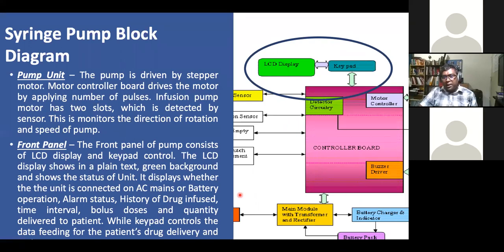On the block diagram, the LCD display and keypad is normally where you monitor all the information, and the keypad is to key in all the information that you want to set, like the syringe size and the flow, what's the rate of the flow you want to run. All that is keyed in here, and you get the display information as well. The display is going to show you whether the syringe is locked properly or the syringe is following the recommendation of the manufacturer, all that. So it's going to show on the display.